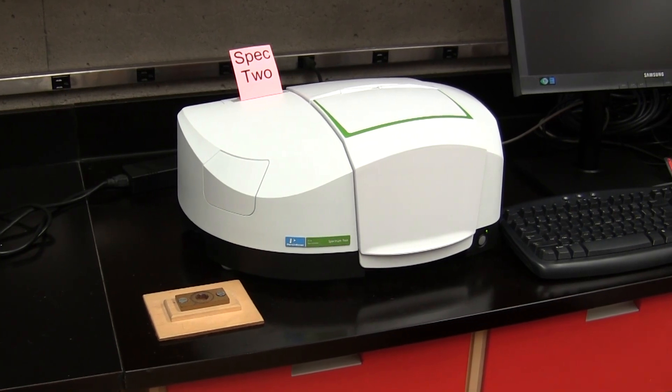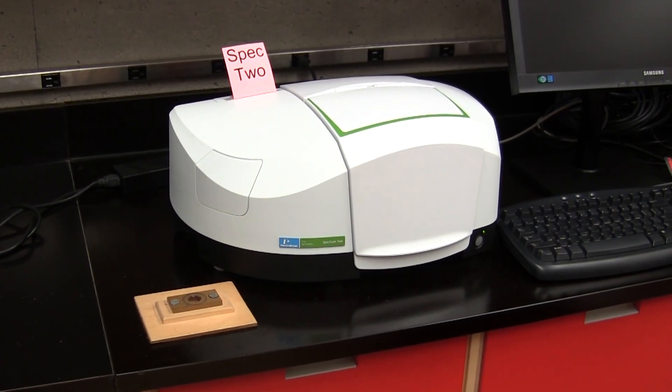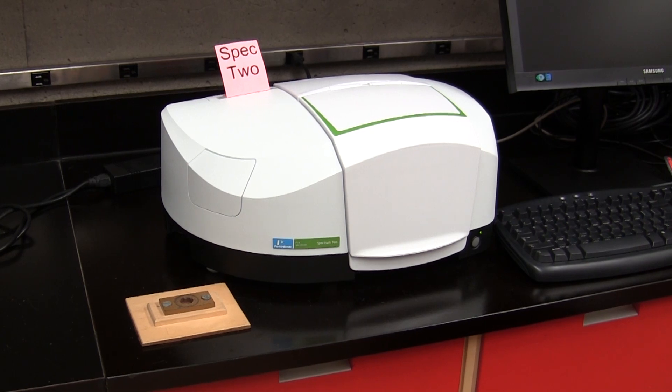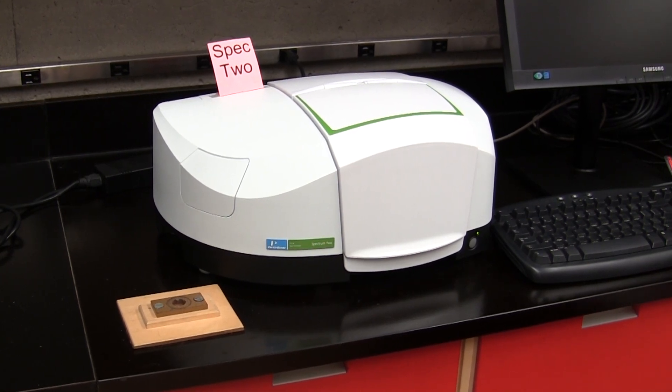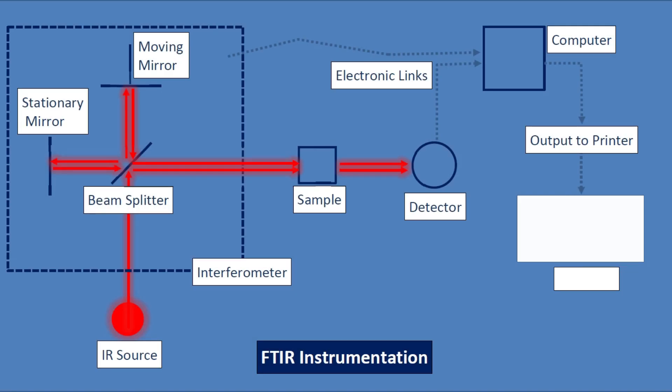Each instrument is capable of obtaining information about infrared radiation at all frequencies simultaneously as the radiation is passed through the sample. This diagram shows the basics of how we obtain infrared spectra using an FTIR spectrometer.